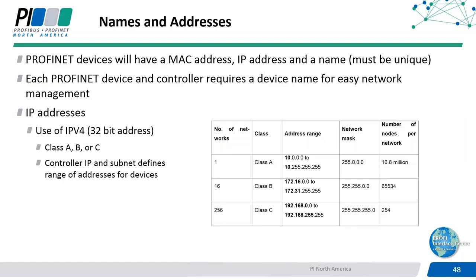All PROFINET devices have a MAC address, an IP address, and a name. We use the name to make it easy to manage your network. You can use different IP classes, A, B, or C, with A having the most nodes per network section and C the least. You can also adjust this further using the subnet mask or network mask to break it down even more if needed. If you need to get into that, check out some tools online like IP addressing or calculation tools to help calculate your ranges for IP addresses.